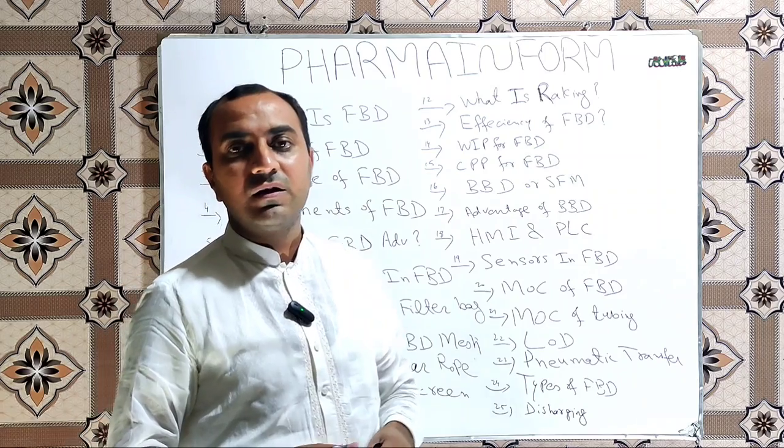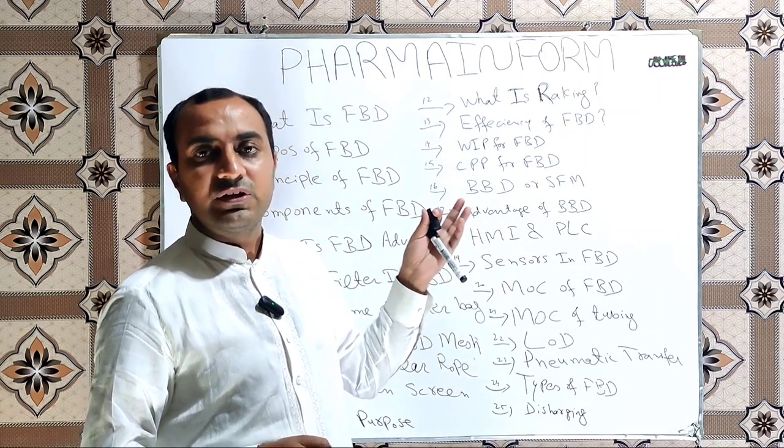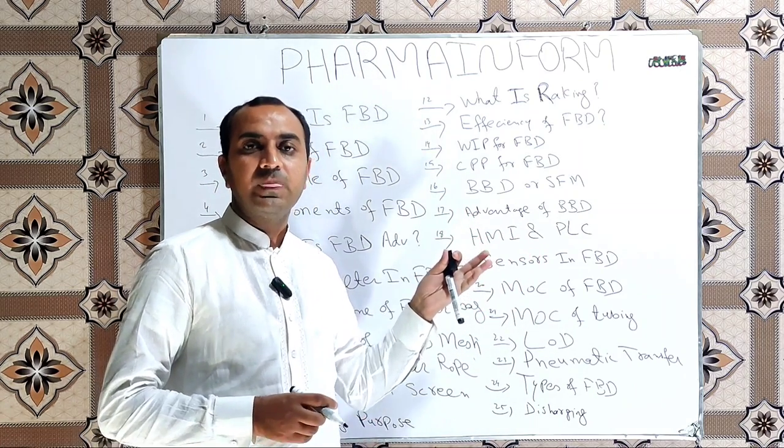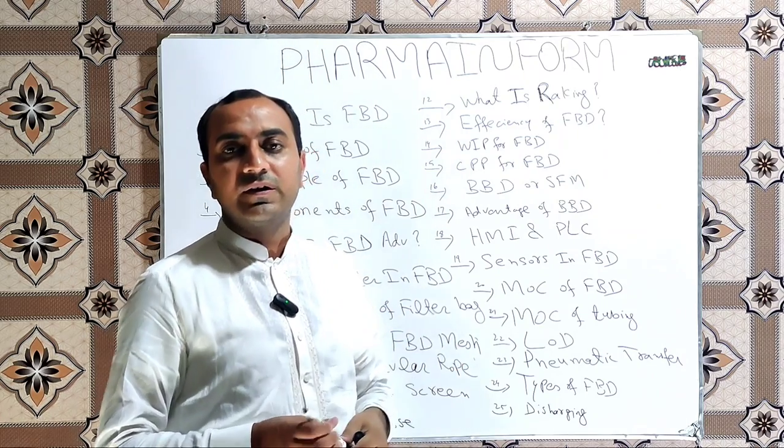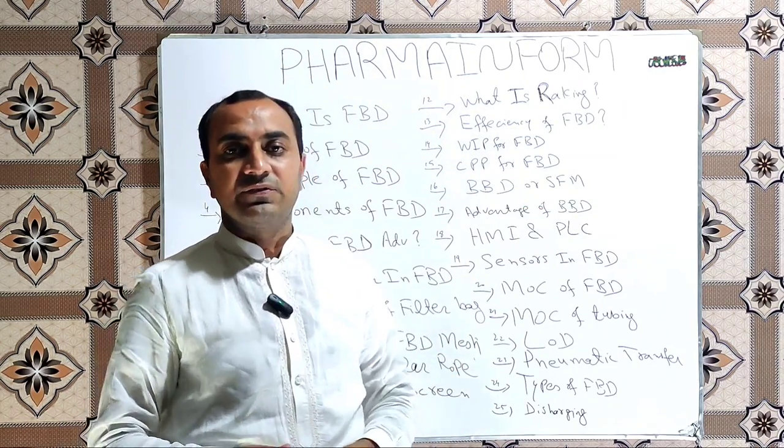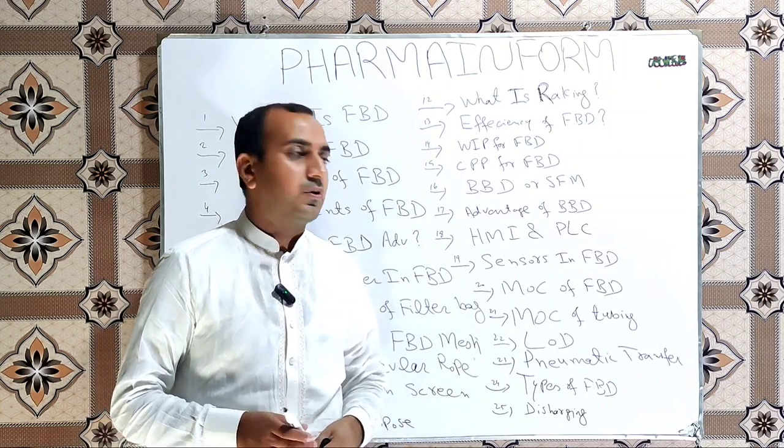If there is any damage to the FBD filter or there is any pin hole in the filter, the powder leakage through the bag to the return duct is detected through these sensors and the dryer is shut down.